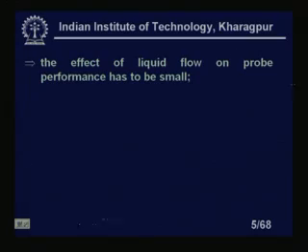Then we have the effect of liquid flow on the probe performance, which has to be small. Suppose we are putting this probe in a liquid which is moving. Because there is a permeable membrane through which liquid may come in, or the electrolyte may go out, those things need to be taken care of.